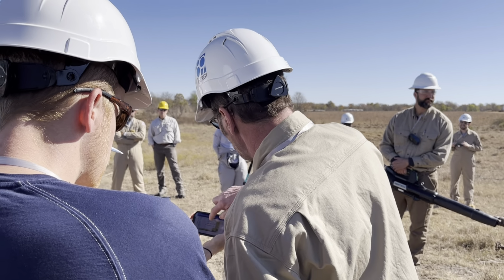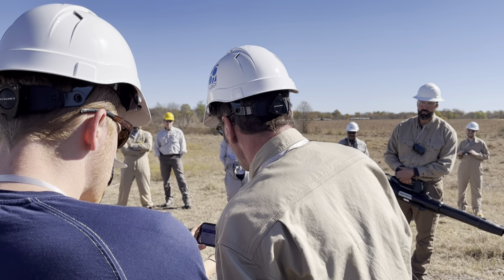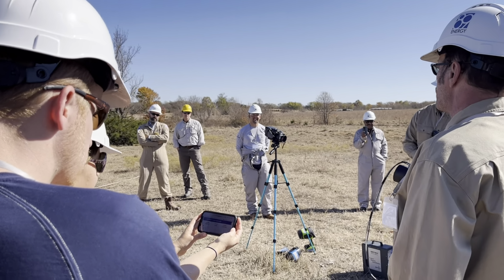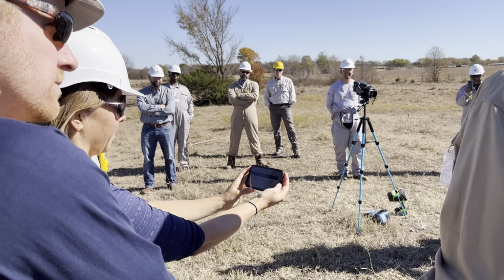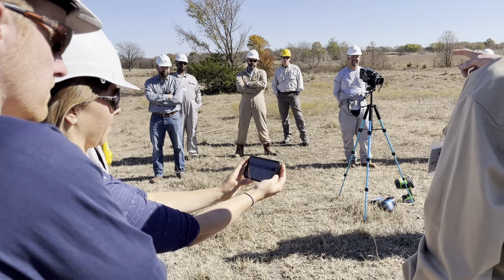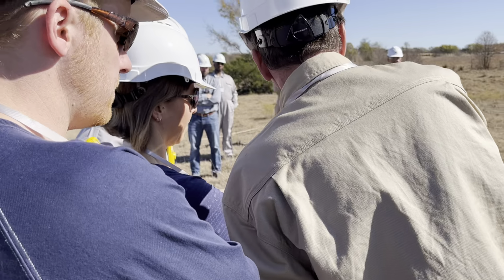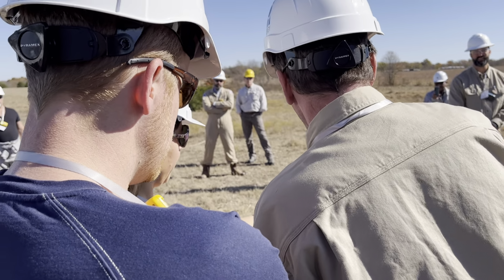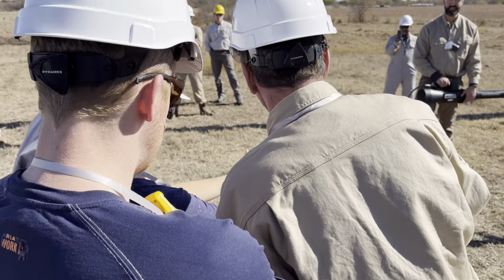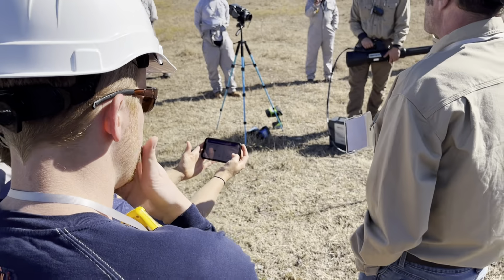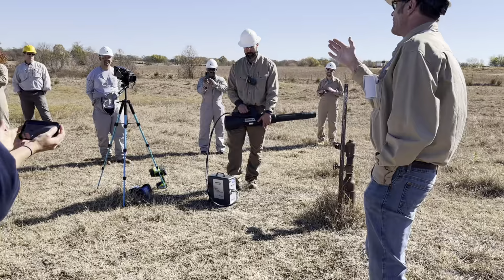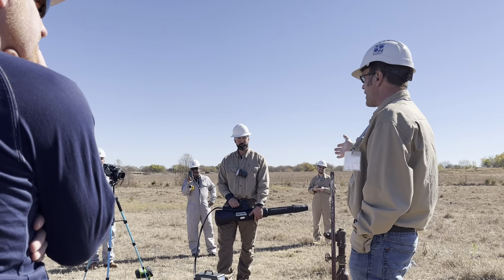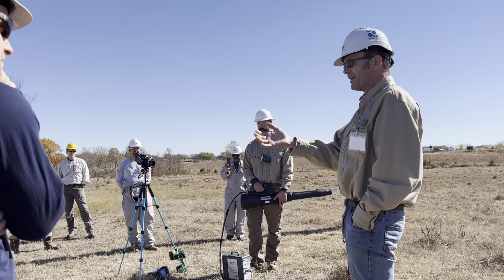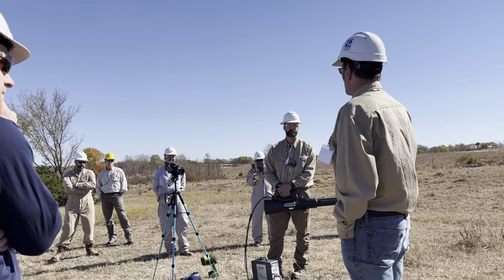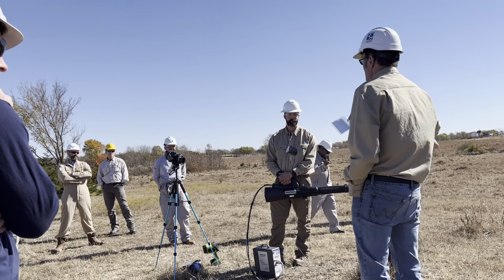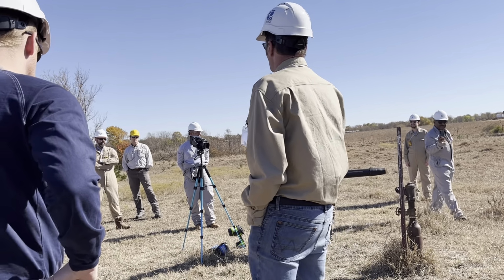But in terms of numbers, we are at 0.01 CFM - that's that leak. Now if you just keep it going and move it off, what's the parts per million? 400. So about 400 parts per million. Now for background, I tell people never to bother zeroing the device unless you know you've got zero background. You could have 20 ppm from the fittings over there, and I guess it's because we're always doing 1 or 2 ppm of zero.